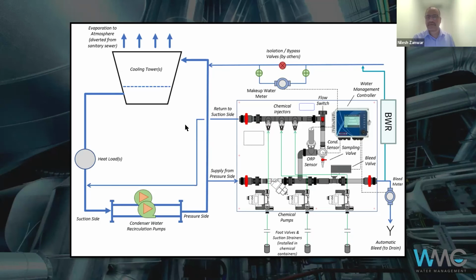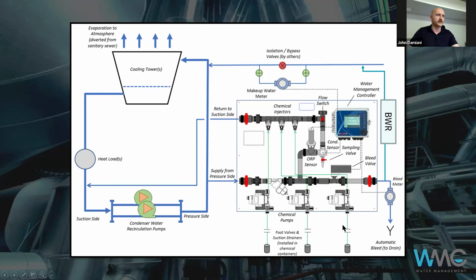On the fluid cooler itself, you would treat this just like one of these systems, because this is an evaporating system that is susceptible to the same things. So as far as corrosion, scaling, microbiological growth, you basically have the same treatment package on this. Usually these systems are a little bit smaller, less than 400 tons, I would say. But that doesn't matter, the requirement's the same. So you'd pull off into a loop, you would have your sensors installed, you'd be feeding chemicals back into that loop, and you bleed off of that.